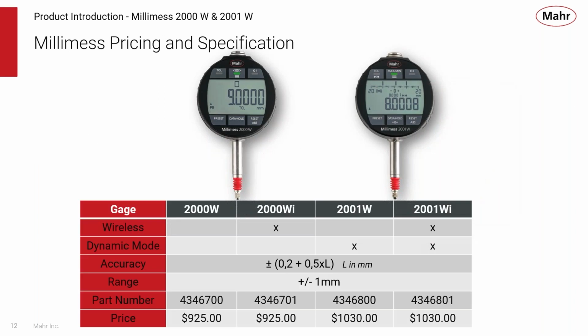So just as a brief little summation of the Millimess line, we have the 2000 and 2001, the W and the WI. You can see the part numbers and pricing. The 2000 with and without the integrated wireless has a list price of $925, whereas the 2001 will be $1,030. And while, again, that's going to seem very expensive for an indicator, you have to keep in mind the level of accuracy you're getting, plus the range. So again, you have that range of plus or minus 1 millimeter for a total of 2, that base accuracy of plus or minus 0.2 microns for a total of 0.4 microns.